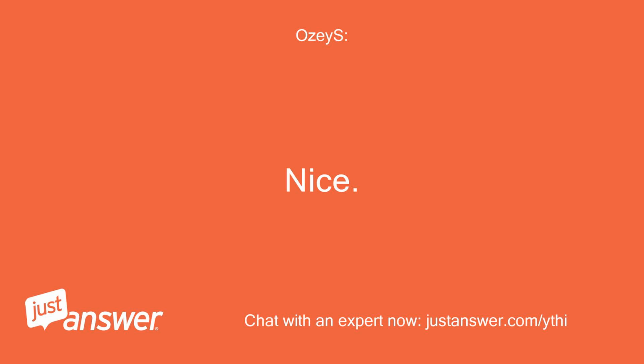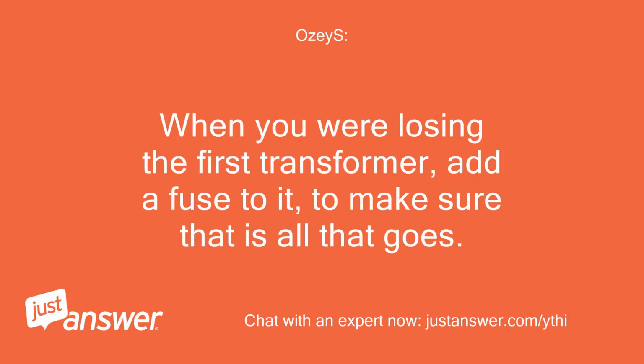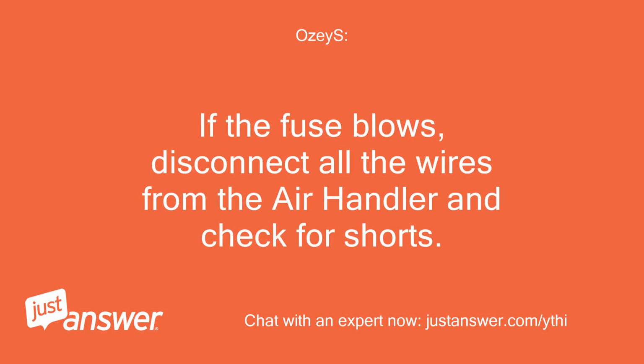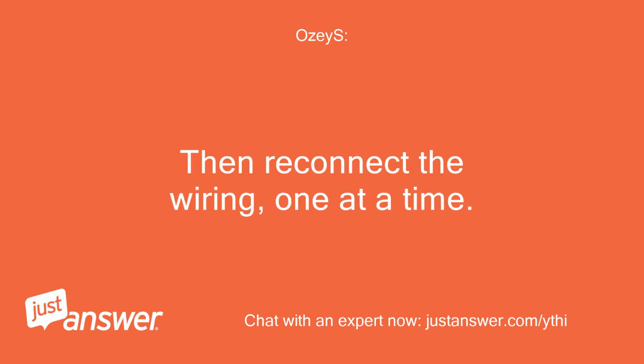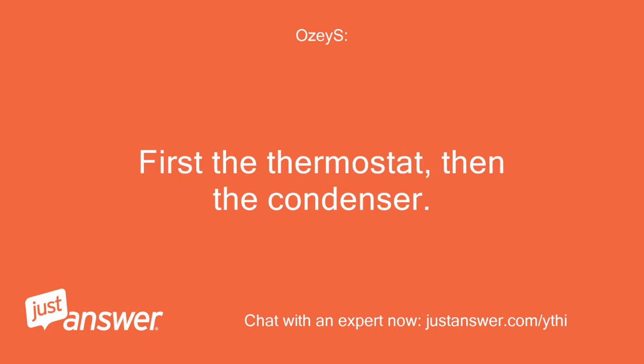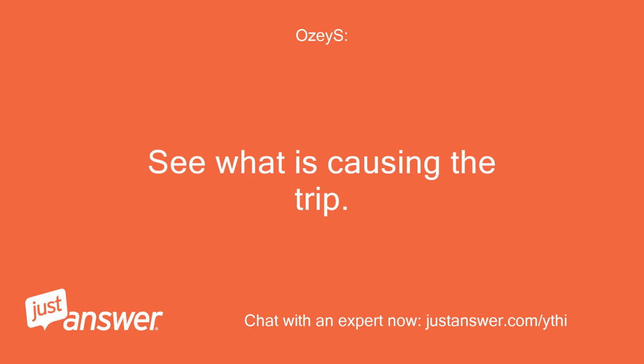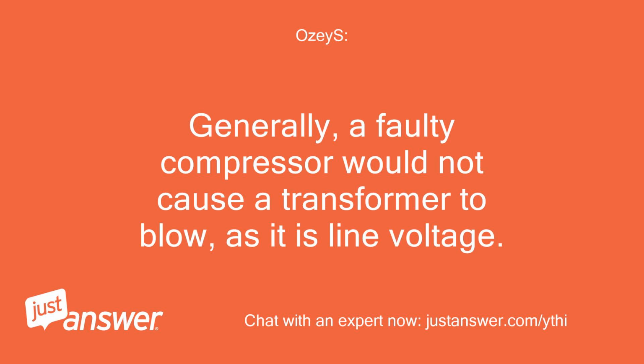Nice. Sounds like fun. When you were losing the first transformer, add a fuse to it to make sure that is all that goes. If the fuse blows, disconnect all the wires from the air handler and check for shorts. Then reconnect the wiring one at a time. First the thermostat, then the condenser. See what is causing the trip. Generally, a faulty compressor would not cause a transformer to blow, as it is line voltage.